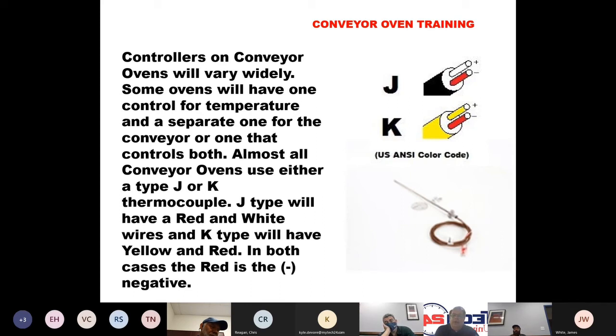But almost all the conveyor ovens use either a type J or a type K thermocouple. The type J will have red and white wires. The type K will have a yellow and red wire. In both cases, the red wire is the negative.